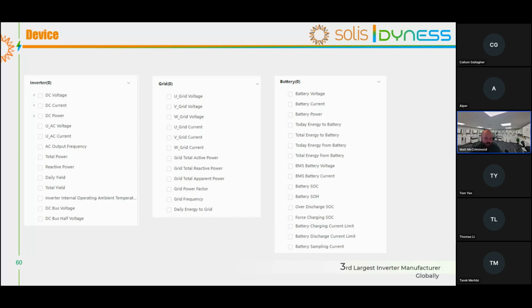What we see sometimes, and not specifically with Dyness but across all batteries, is jumps in SOC values based on recalculations of the BMS. That could be that the customer hasn't had enough PV to charge their battery for 2 months, for example, so it's sat between 20% and 40% over winter and never had a chance to go above. What we would typically do there is select, on the right-hand side in the last column, the battery charging current limit, which is a key indicator that it's a temperature-related issue.